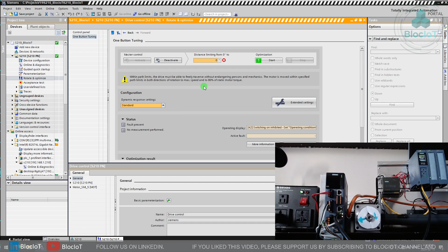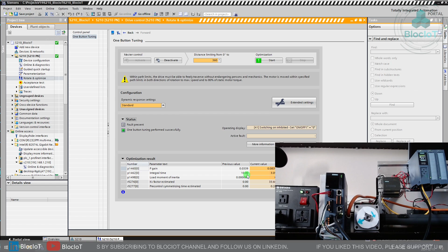And as you might hear the noise, it's just adjusting or tuning the PID control. And voila, as you can see, it has significantly adjusted my integral time or the parameter I in my PID control. That's the optimized value for the PID control for this configuration. So after doing that, just deactivate the drive and make sure you hit this icon over here to retentively save the drive parameters from the TIA Portal to the drive. Okay, that's it from the drive side.